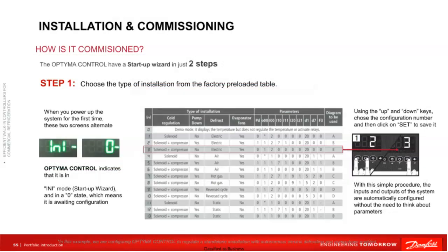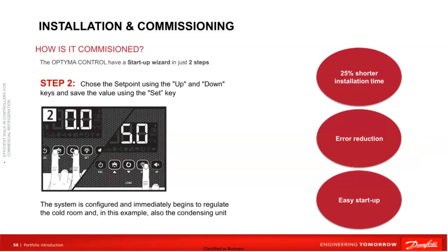Now, let's move on to the commissioning process. Commissioning can be divided into two main steps. The first step is to select the appropriate application that is responsible for cooling regulation, type of defrosting or shutdown with pump down, and control of evaporator fans, depending on the need and configuration. The next step is to select the set point value and confirm it, and then the controller takes control of the condensing unit and the cooler.